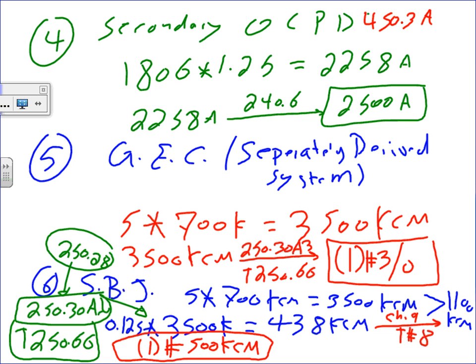And I injected the grounding electrode conductor and the system bonding jumper because if you have a transformer, these two things you must be thinking about. How are you going to size the grounding electrode conductor and the system bonding jumper? And everybody knows what they do, guys. They take the neutral bar, the ground bar inside the transformer, and they bus them together, either with a copper bus or with a cable. Just tie them together. And then they take a grounding conductor. In my case, it's 3/0, and they go all the way to the steel and connect directly to the steel through a connector. That's how you create a separately derived system.